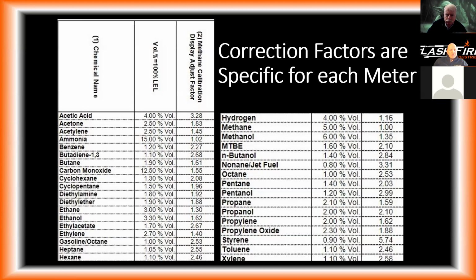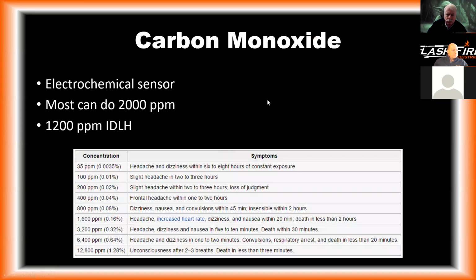So that's why I don't get too into the correction factors, but it is good to know that they're out there. Okay. Any questions on that? All right, so that's our LEL sensor. Our carbon monoxide is an electrochemical sensor. Yours and most CO meters will do up to 2,000 parts per million, some less, some more. Remember, the 1,200 parts per million is our IDLH, so we are going above the 1,200 parts per million.